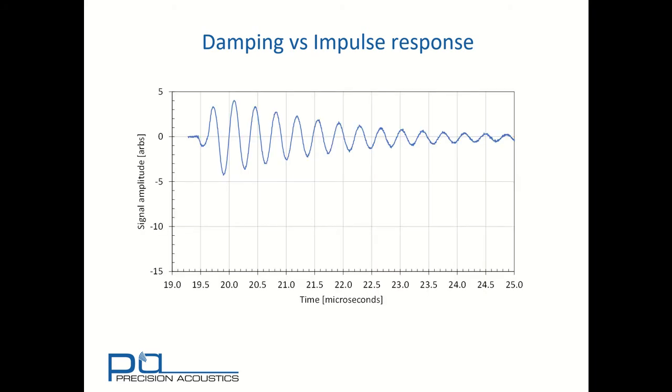Let's have a look and see how that translates to the time signature output by the transducers in response to an electrical impulse. This is the narrowband, low damping transducer. We can see that it's got quite high amplitude but a very long burst, with the ring down being some 12 to 15 cycles.